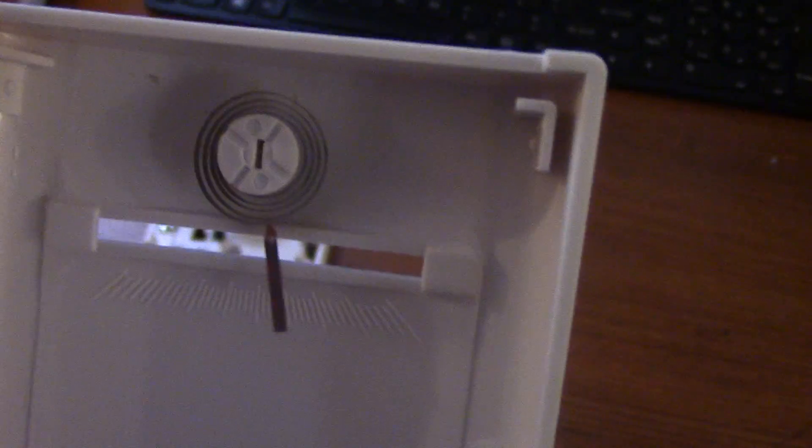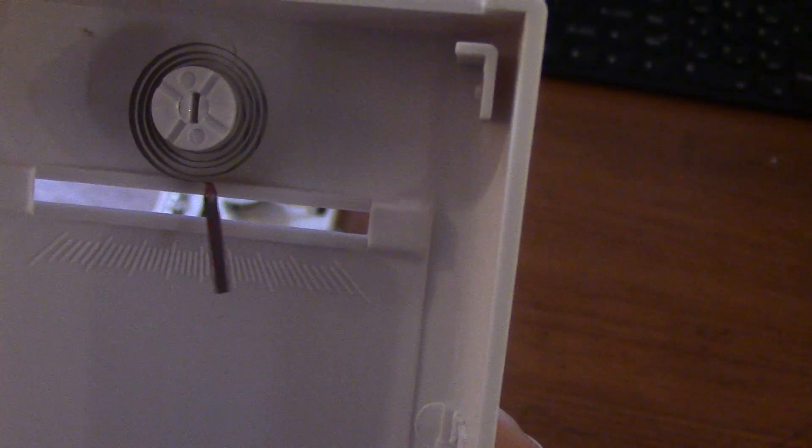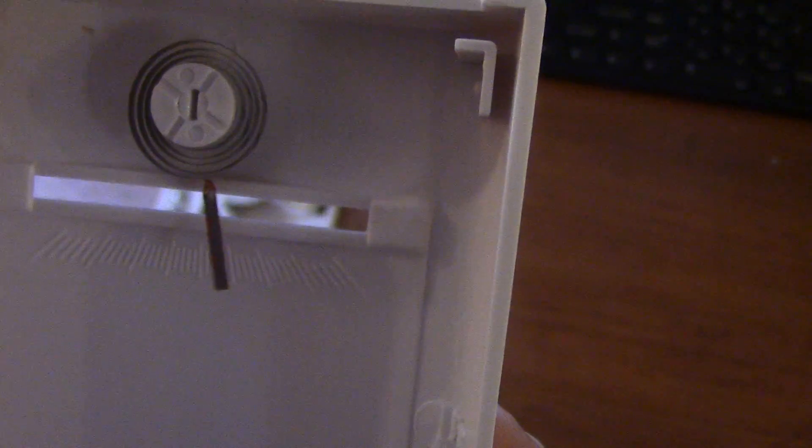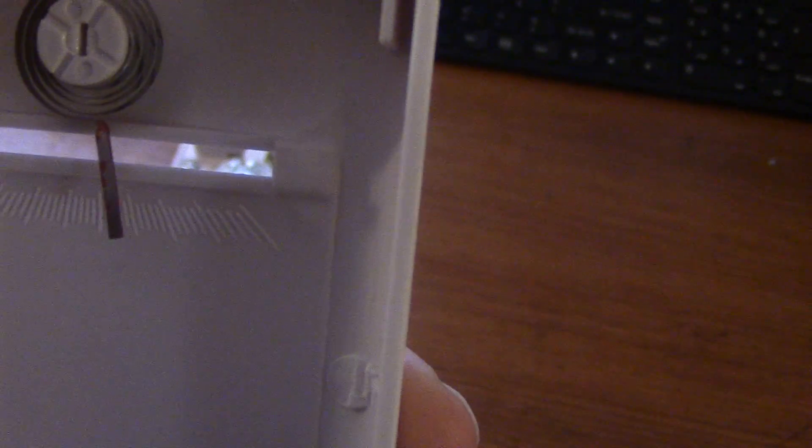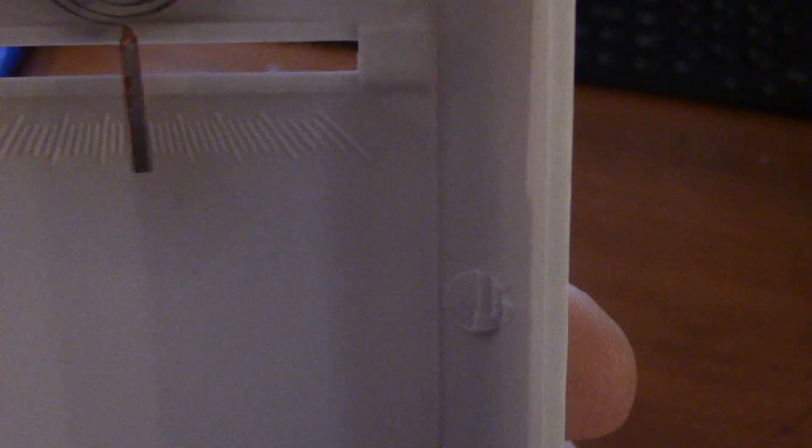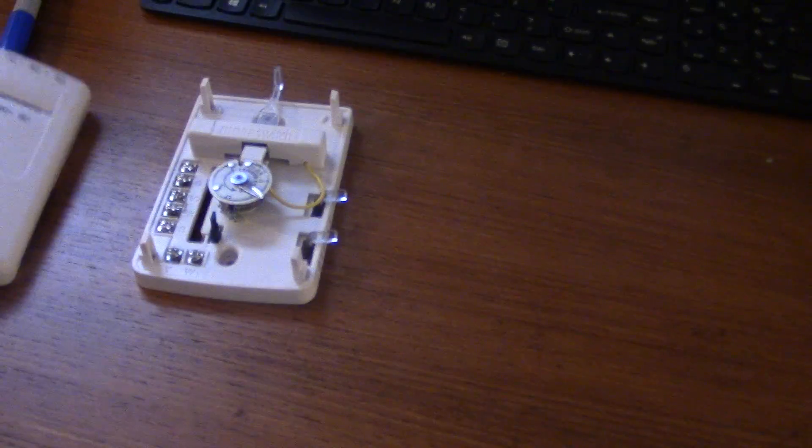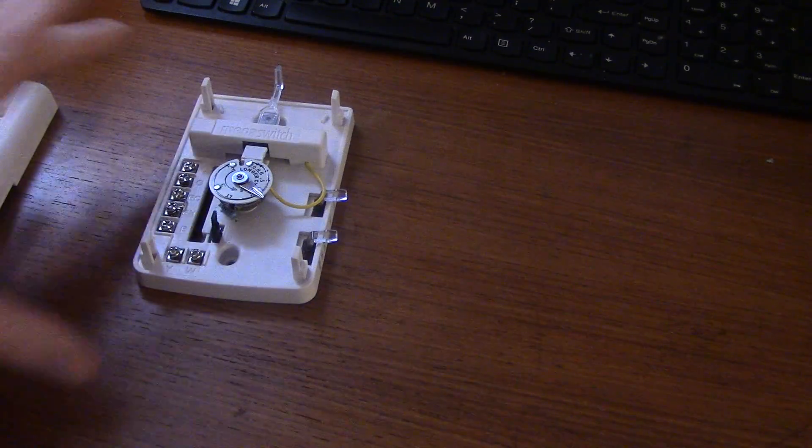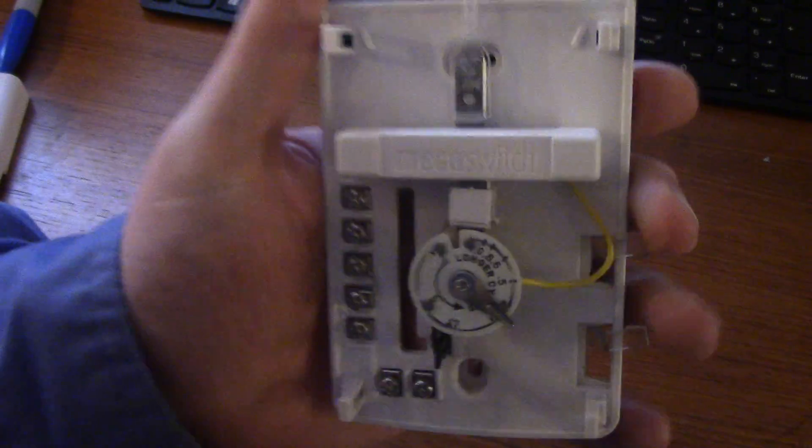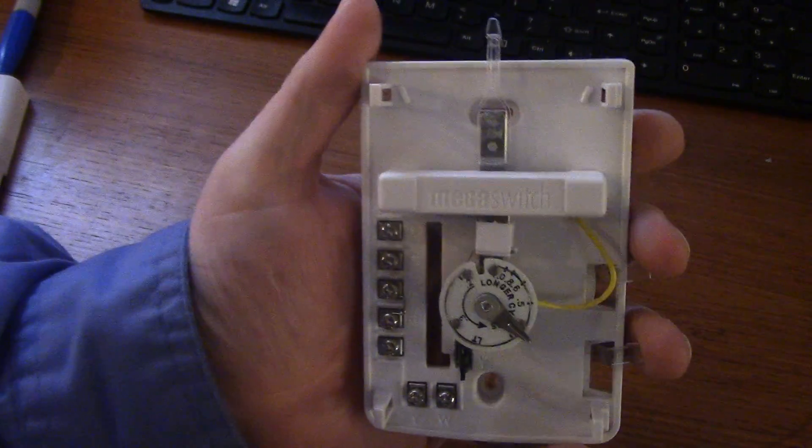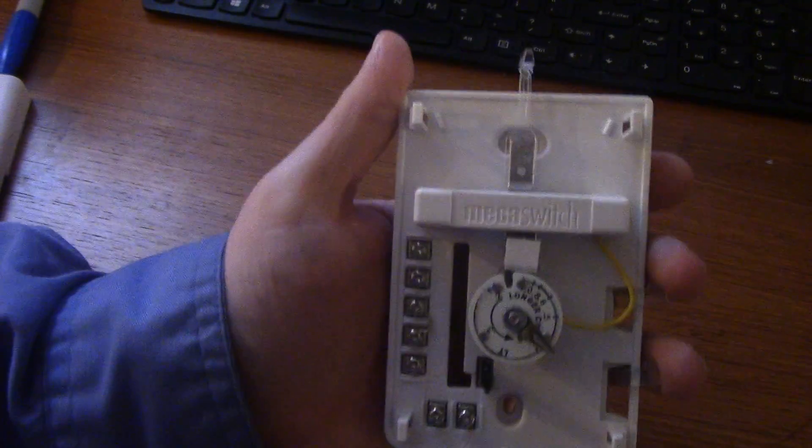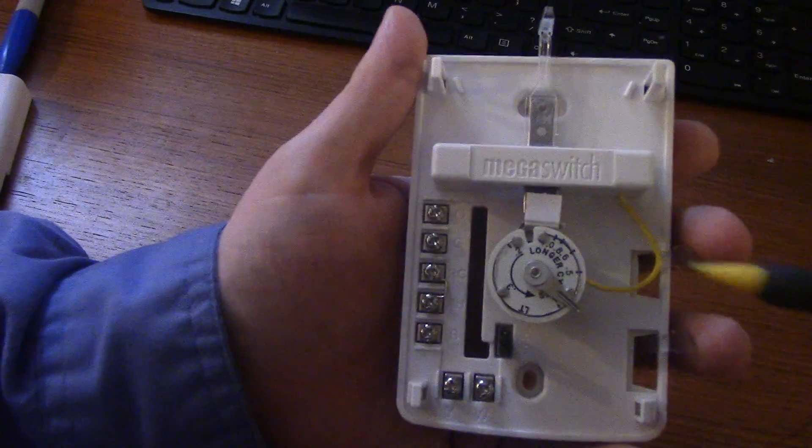All it is back there is you have a little bi-metal strip - you have two dissimilar metals that expand and contract at different rates. In fact, let's see if we can make it move here just by blowing on it. Moves - that little bi-metal portion will expand and contract at two different rates to tell you what temperature you are in the house. Here is what the thermostat looks like under the cover.